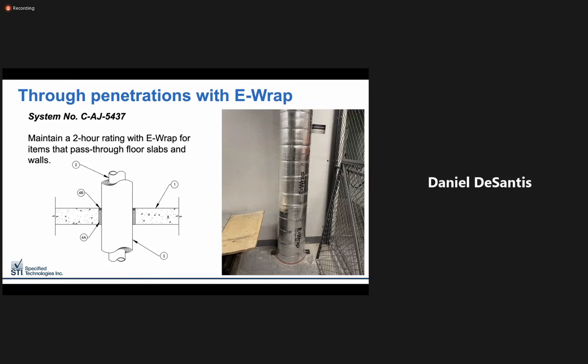In this case, an 8-inch double containment fuel oil line exits the CMU shaft directly beneath the floor slab. Using this typical detail, we are able to support the use of E-Wrap transitions from shafts of unlike materials. This is also a great system to maintain a continuity of protection through cast-in-place walls as well.